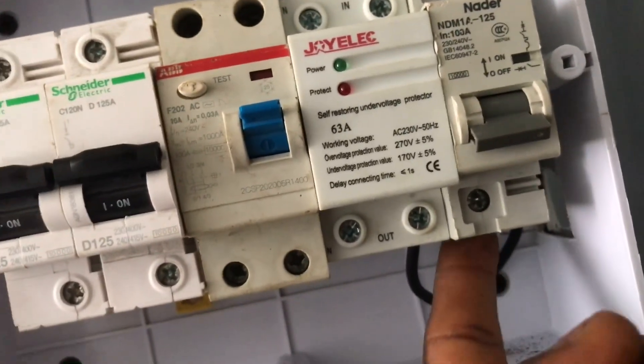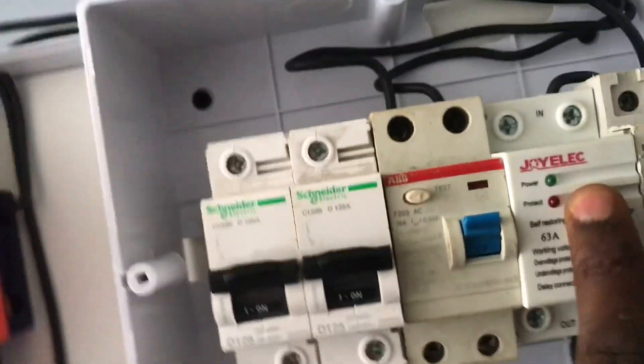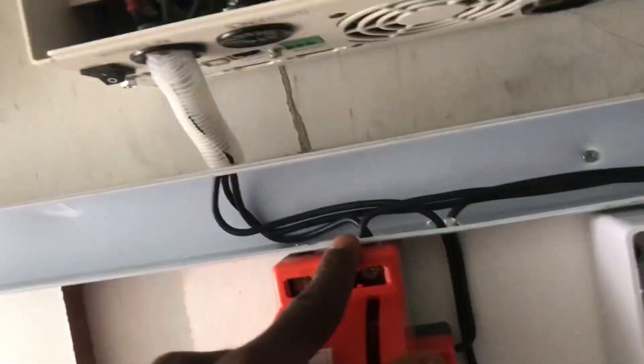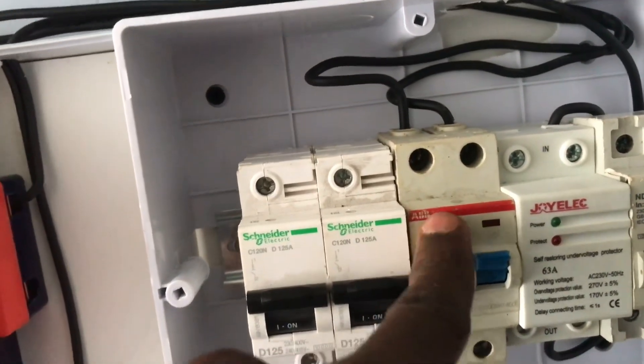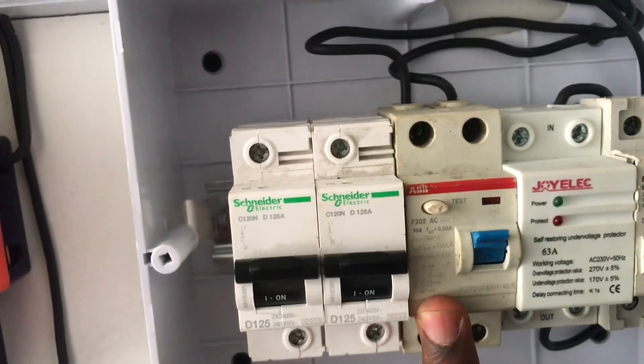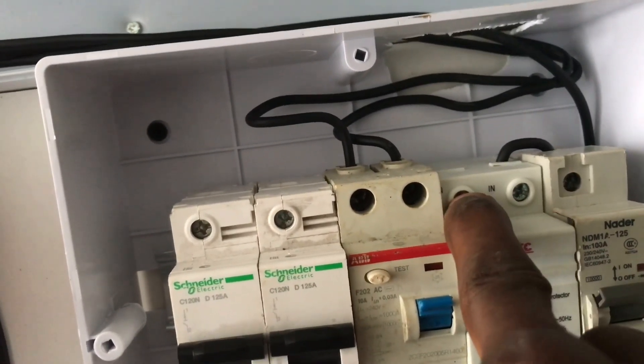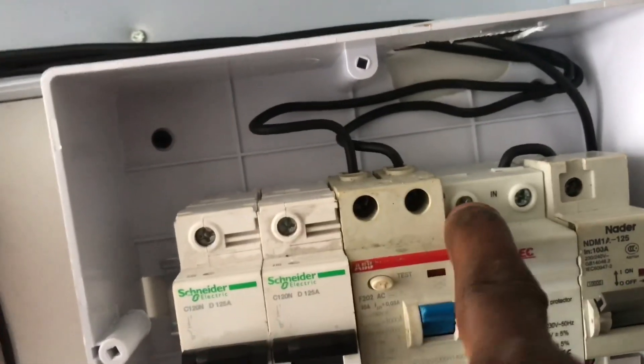So this is our input — I have already loaded. Short power from the house enters here. So once it's on, it will contact from here — from this area — and it will be live. Then it will come out going to our inverter. So the neutral came straight to this place. So here is our output. This breaker is for our output, so this is serving as protection for our output. So the neutral just went direct.